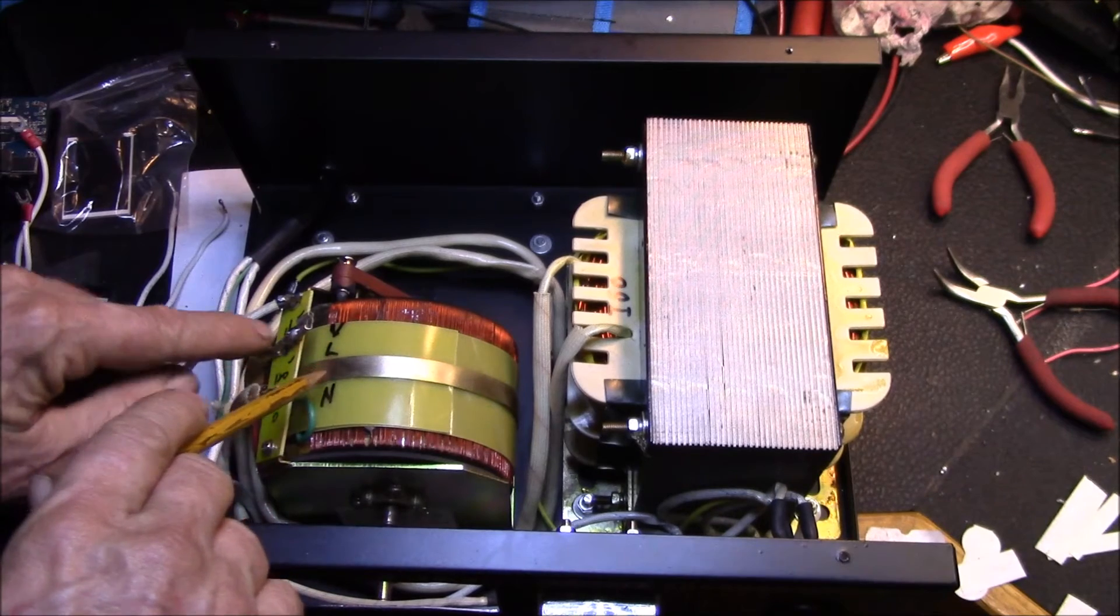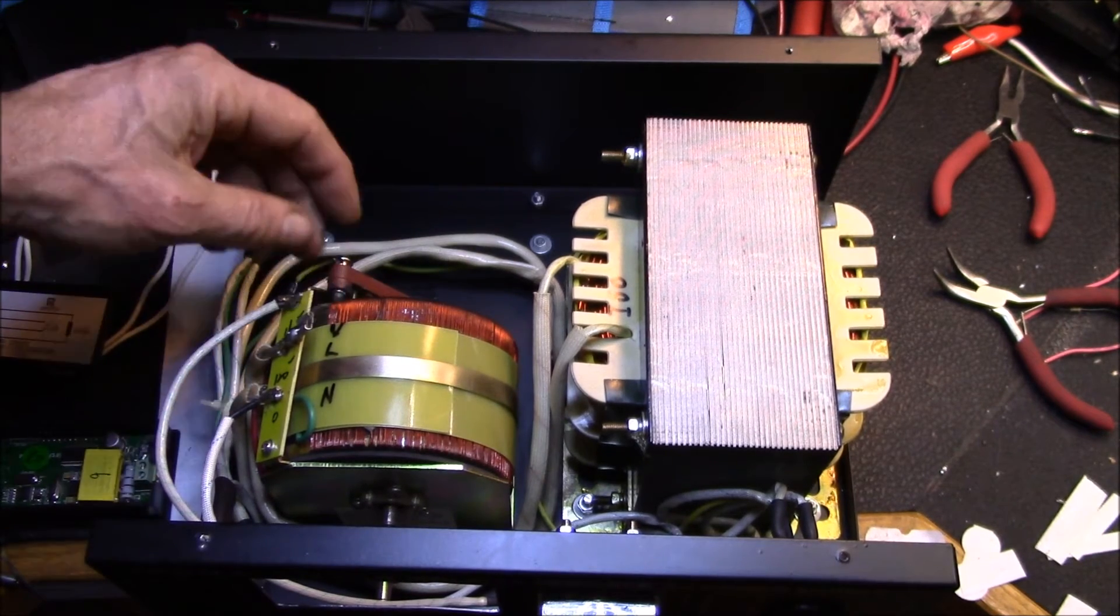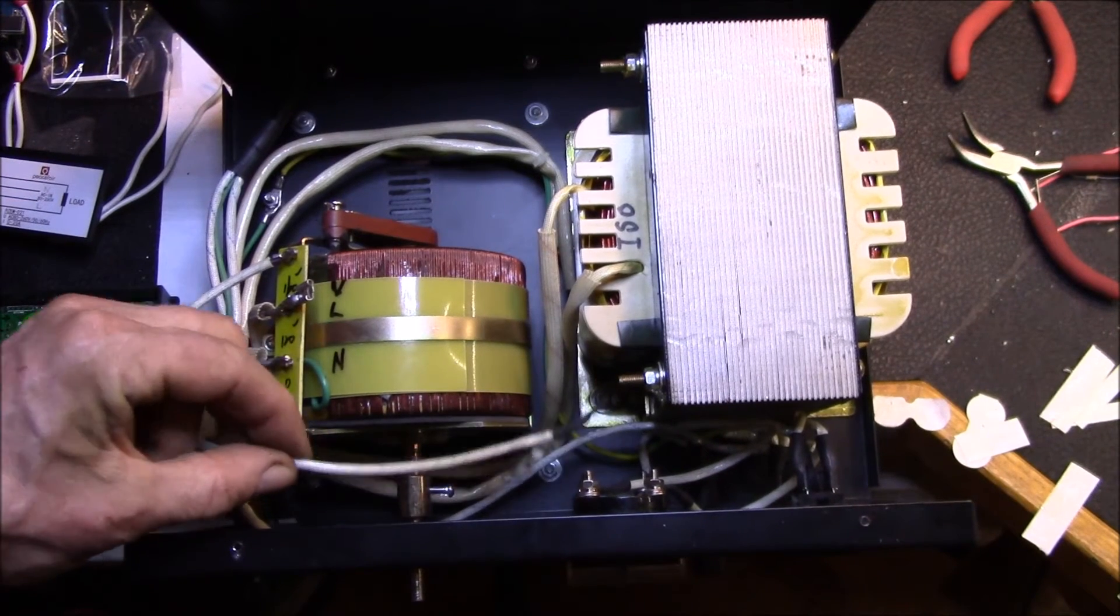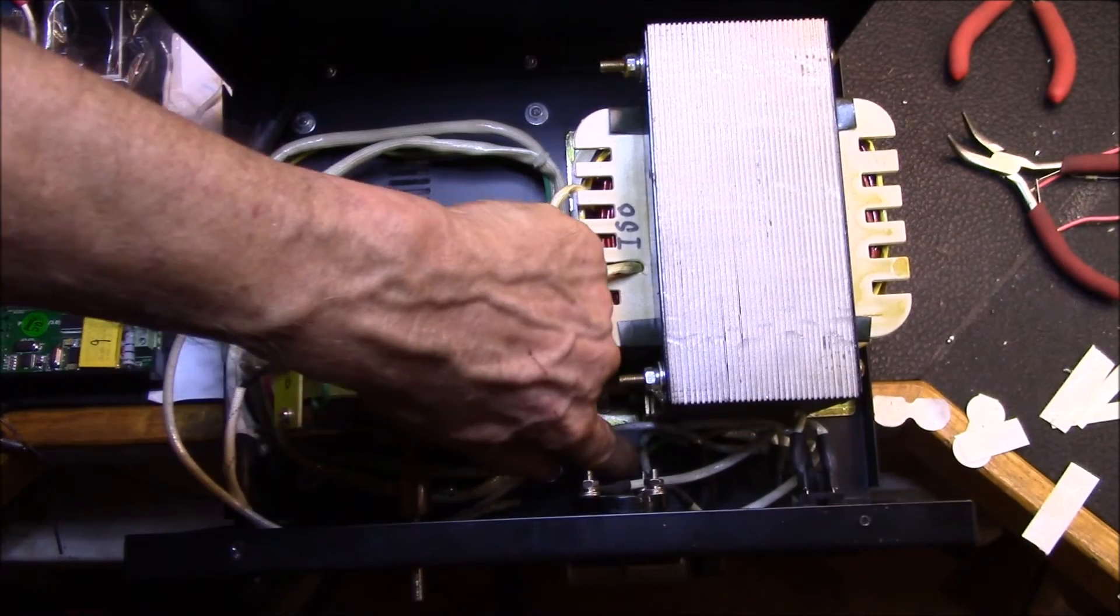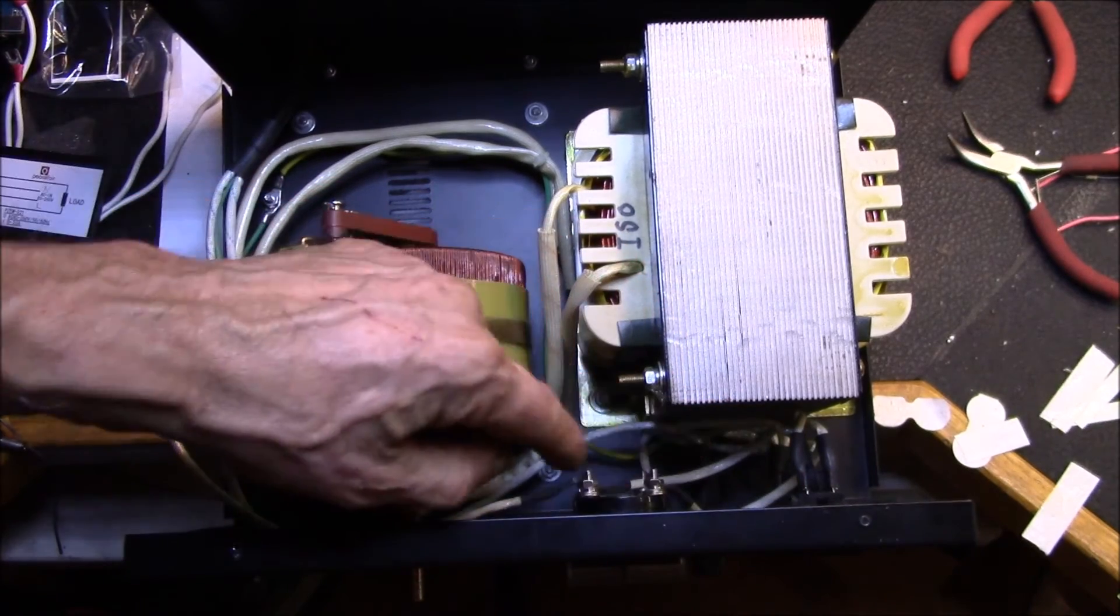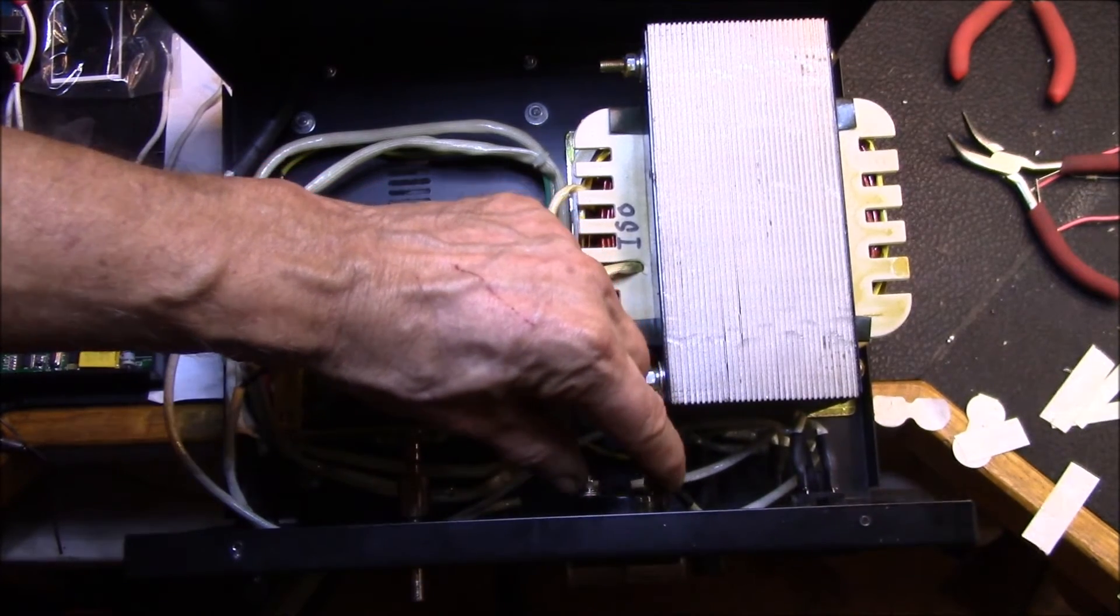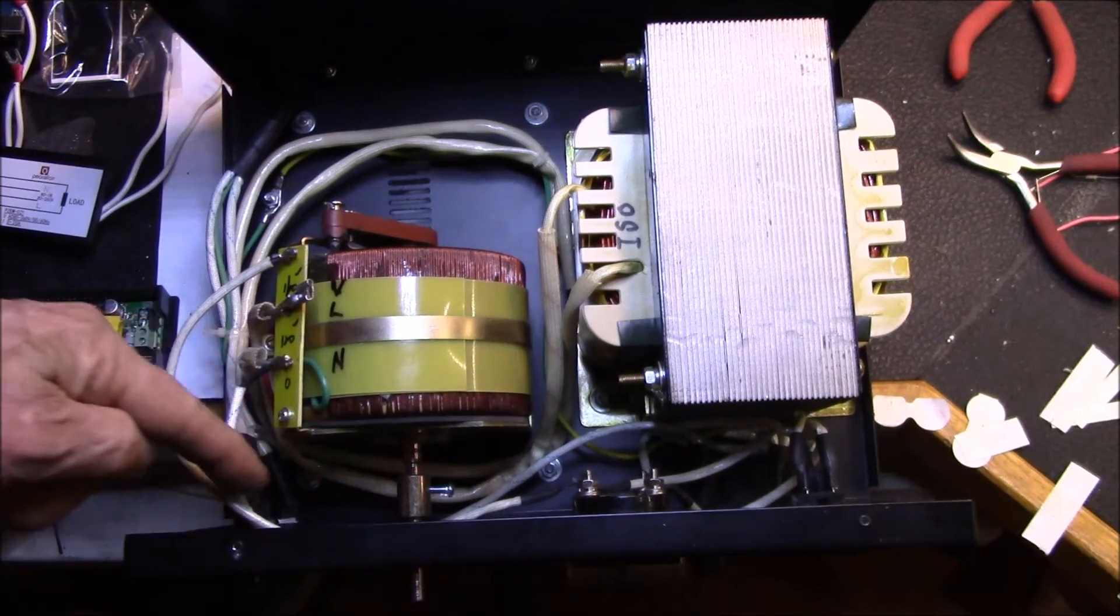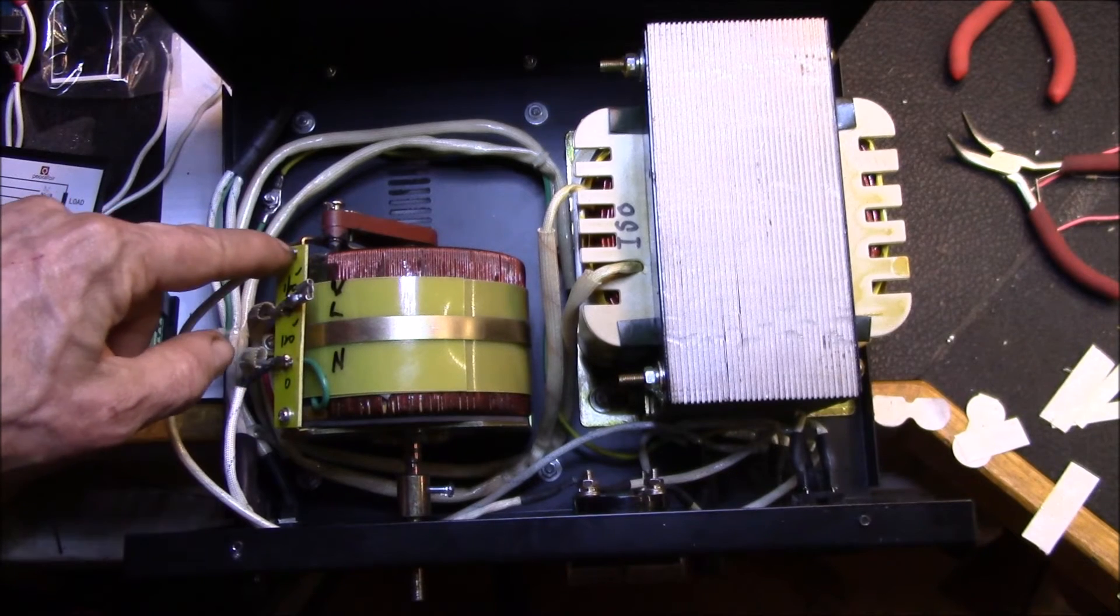This is where you get your variable voltage. This is the neutral connection and then 120, so I actually labeled them neutral and line. This pin here picks up wherever this sliding contact picks up voltage, all the way from zero clear around to 150 volts. Here's your ammeter wire, comes from the variable voltage on the variac to the ammeter. The ammeter's other side goes over to the power plugs, the receptacles, and feeds the hot terminal. Then the neutral terminal comes over here to the voltmeter, so the voltmeter sits between the hot and the neutral on the receptacles. There's a fuse down here, and then that comes back over to here to complete the circuit.